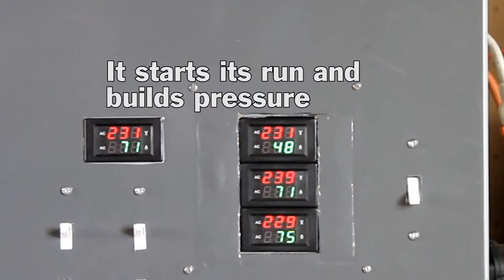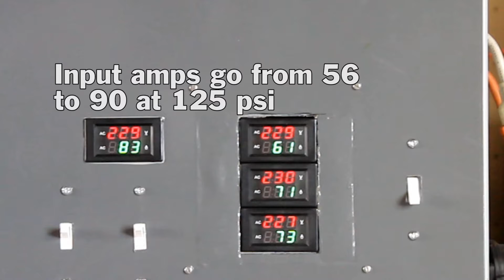We started off at 56 amps, and as pressure builds it keeps ramping up. You'll notice it was 74, 75 amps on one leg, 70 on another, and lower amps on the third. What happens in these cases is two legs are going to be fairly high and one leg low, same as you get with a rotary converter or a lightly loaded motor.